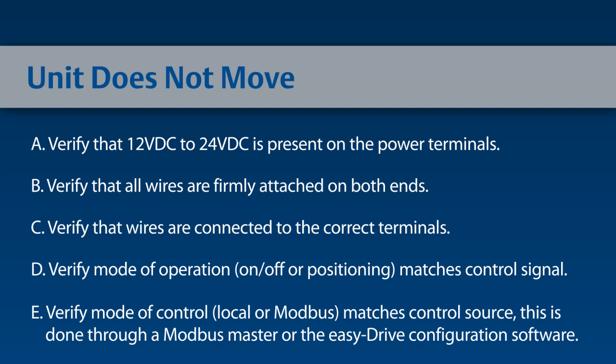Verify the mode of operation — on/off or positioning mode — matches your control signal. Verify the mode of control, either local or Modbus, matches your control signal. This can be done through Modbus Master or the easy-Drive configuration software.